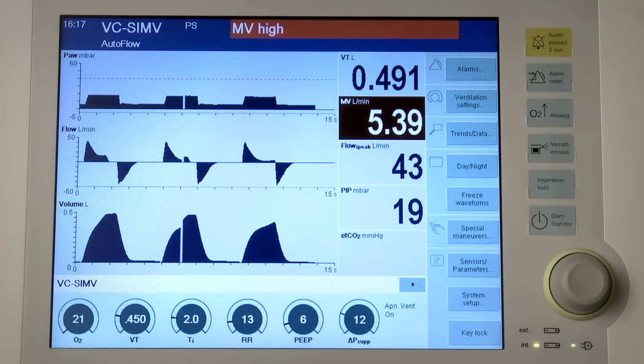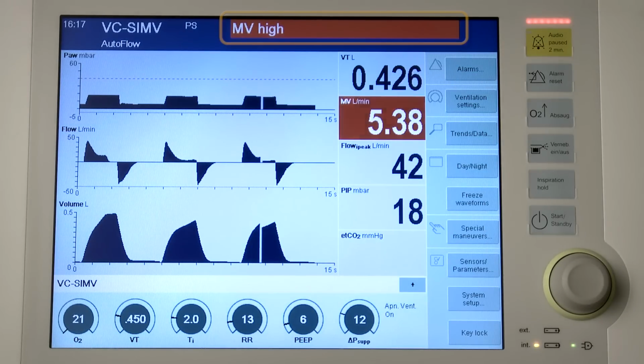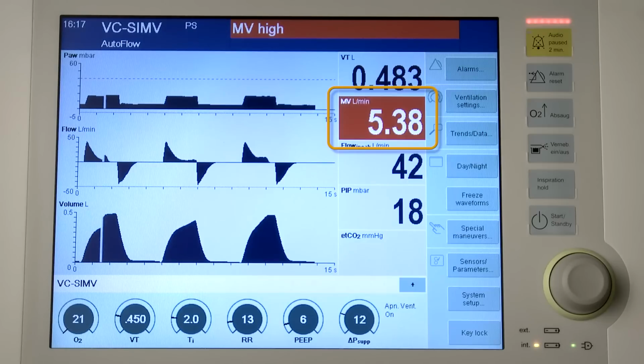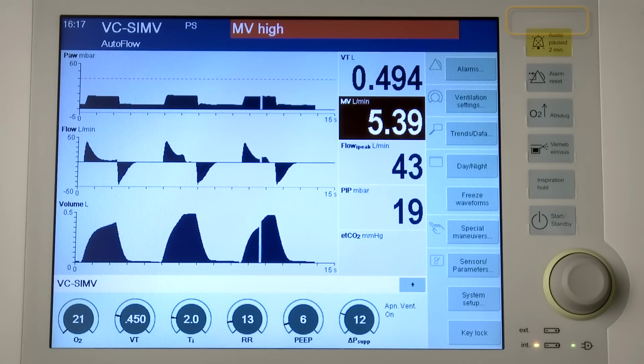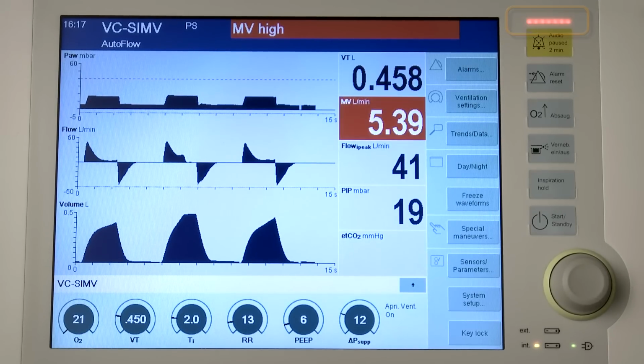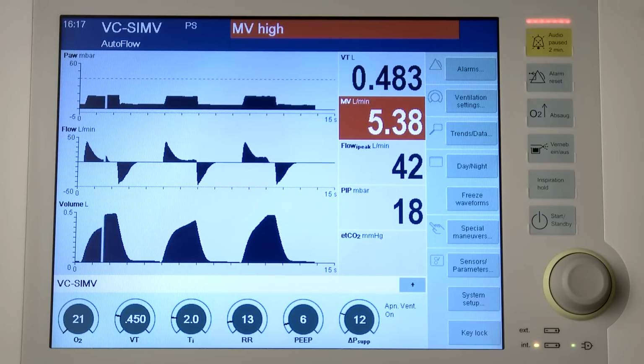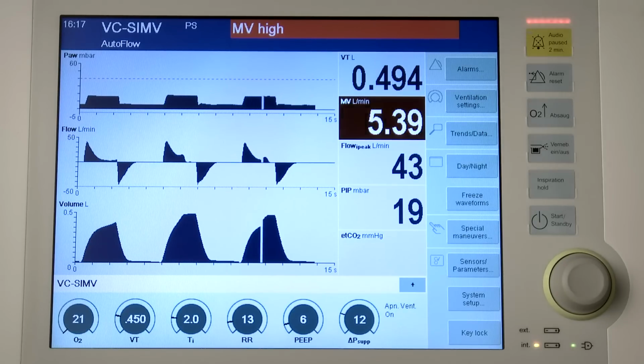Savina 300 displays the following visual and acoustic alarm signals. First, the system displays the relevant alarm message in the alarm message field of the header bar. Second, the parameter field of the parameter triggering the alarm flashes. Third, in the alarm's dialog window, the corresponding measured value flashes. Fourth, for high priority or medium priority alarm messages, the corresponding LED flashes on the control panel. The background color of the alarm message field indicates the priority of the active alarm. If several alarms occur simultaneously, the alarm with the highest priority is displayed first.